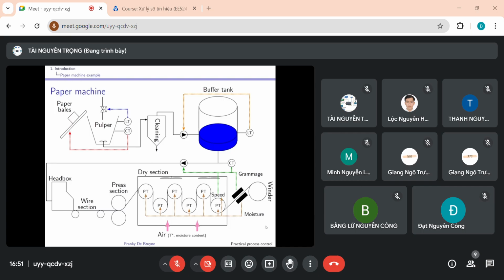In this drawing, it looks as if the internal model controller is directly interacting with the pump. In reality here, you have a flow transmitter, and you also have a local stock flow control loop. So what is happening is that you have an internal model control. This is the master. It sets the stock flow set point, and this local loop is implementing this stock flow control.